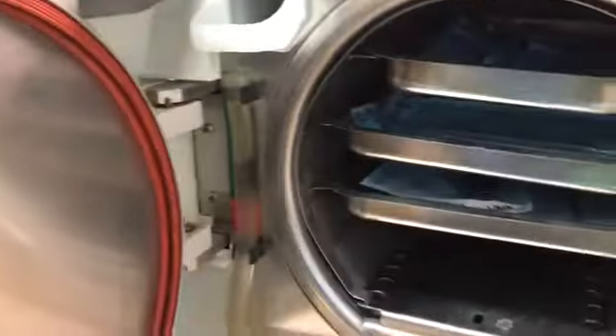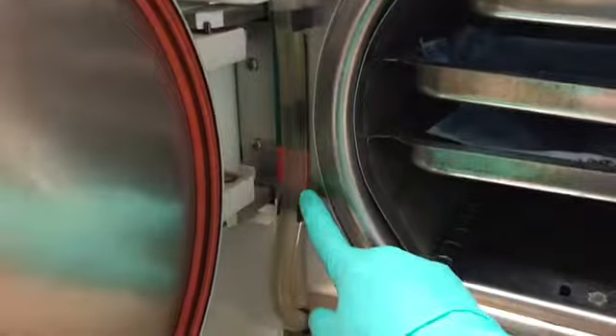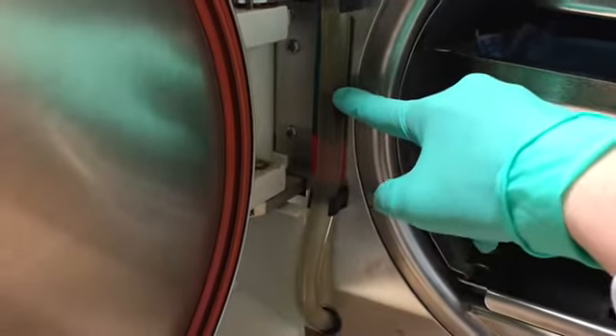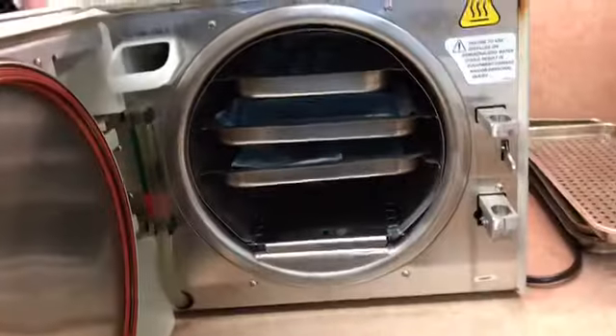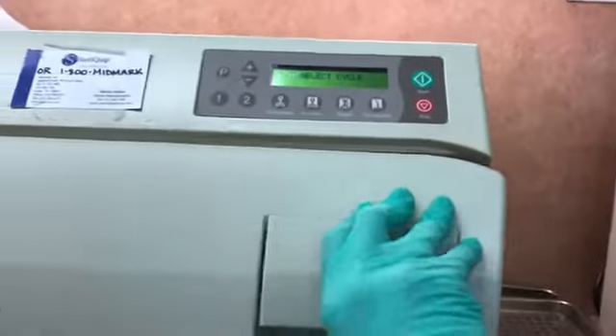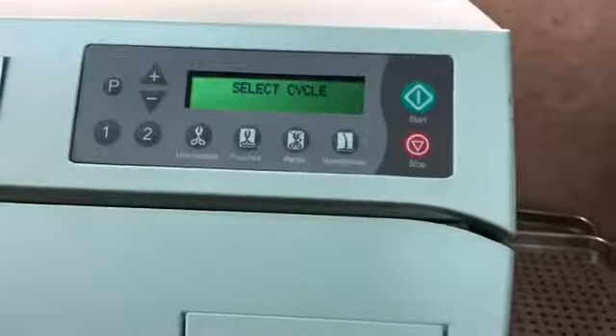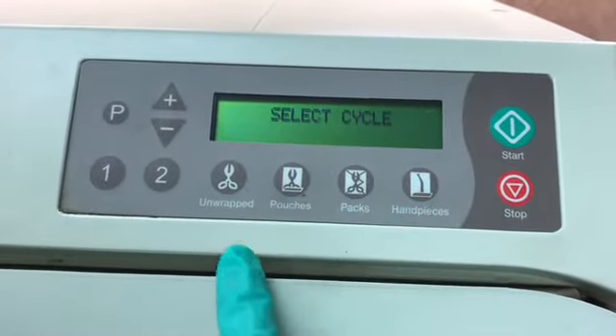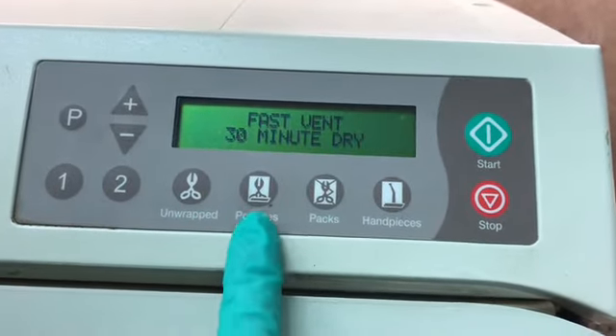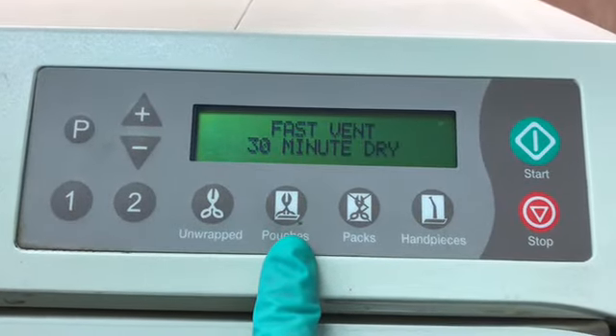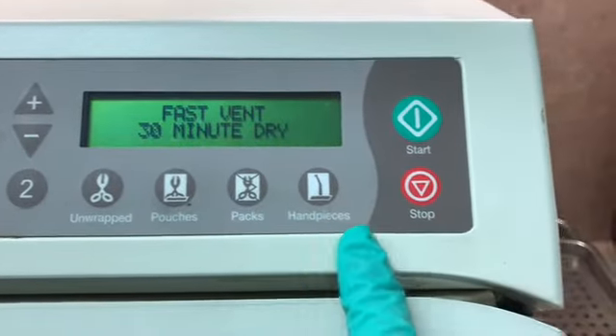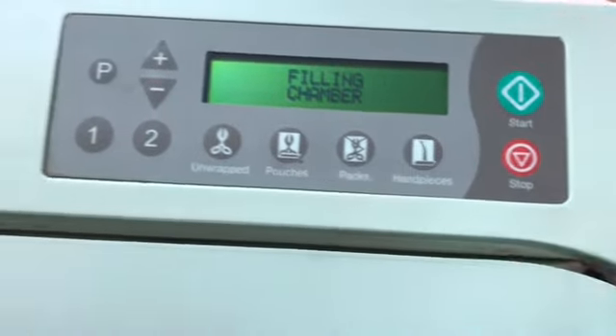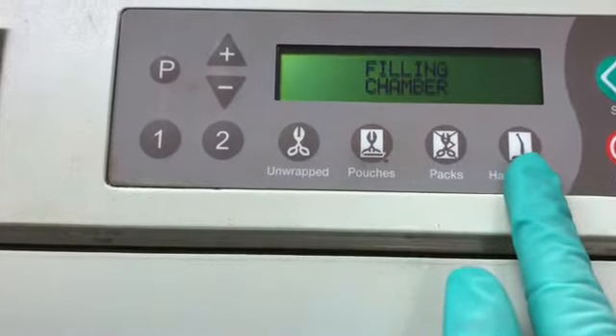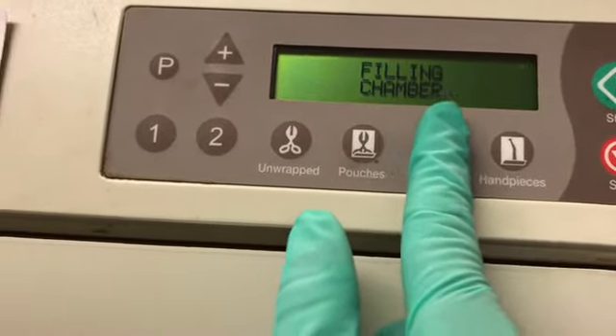So the next step is to make sure that the machine is going to work properly. You're going to look at this distilled water tube. The line is up to here, and you want it in that green line. If it is below, you need to put some distilled water in here and fill it up. So the next step is just to close the autoclave. Okay. And the way this one works, it's all preset. What I'm doing here is pouches, so I will just push the button here. It says 270 degrees Fahrenheit for 5 minutes. So then I'm going to push start. If I were to do any of these other buttons, it would have different temperatures and duration.